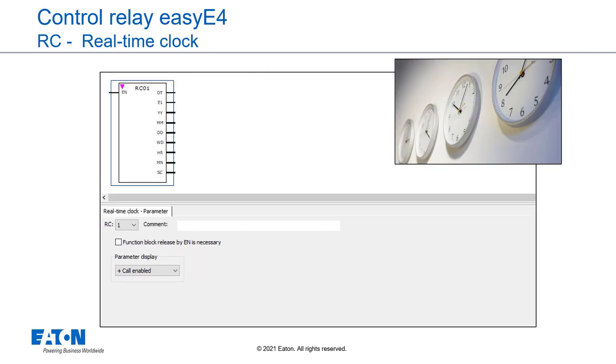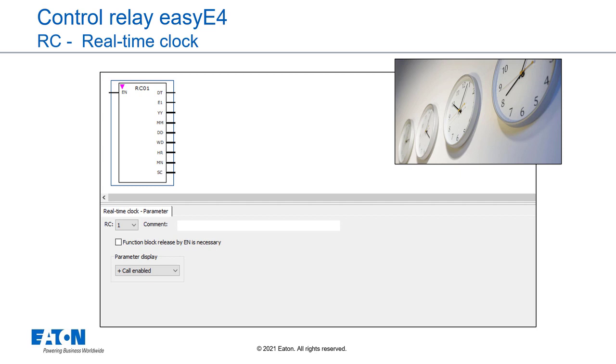easyE4 provides one real-time clock function block, RC in short. This function block can be used to read the date and time value of the device's real-time clock. This value is output in seven individual parameters that can be processed further individually. If the function block is enabled, the date and time value from the device's real-time clock will be output at the function block outputs.